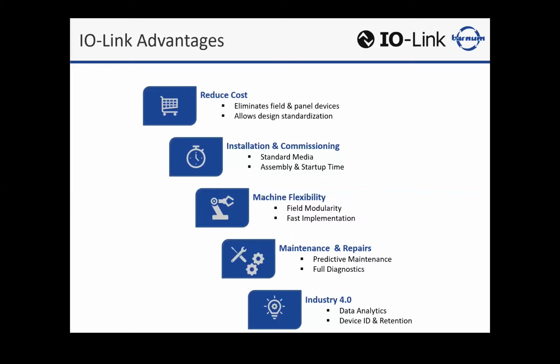in your equipment. Installation and commissioning, it's all done through connectivity for the most part. Simple IP67 circular connectors, providing network communication and aux power. So very easy to lay out and actually install the system. Also, assembly and startup time is greatly reduced because everything is connectivity. But also, furthermore, the diagnostics and troubleshooting that IO-Link lends itself to at a very simple level allows that uptime of commissioning to really be appreciated.